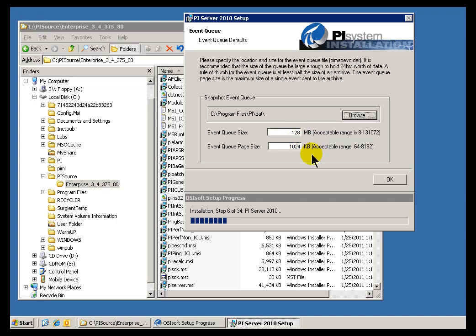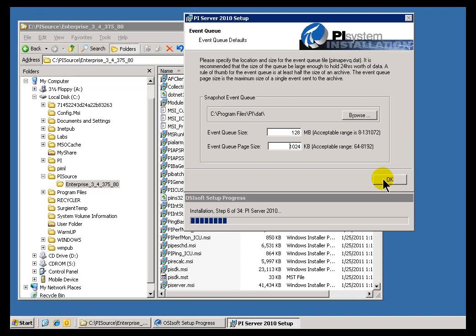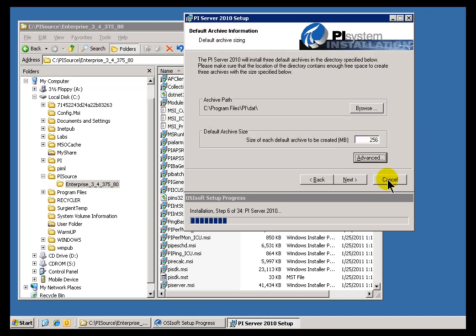Now the Event Queue Page Size really has one impact. It limits or it's the boundary of what you can store in a single annotation. I should not say it only has one impact, but that's the thing that might affect you other than some subtle performance differences. So the Event Queue Page Size is going to limit the size of your Annotations. Now 1024 Bytes or 1K, that's big enough for most people's uses, but if for some reason you've got very large Annotations that you need to do to your PI Data, then you can make this larger to accommodate that. The general rule of thumb here is to leave these the default, because we really don't expect anybody to change this unless there's some problem. Unless you know in advance you've got a very unusual kind of profile of how much data you're bringing in and the size of that data, I would leave these two alone.